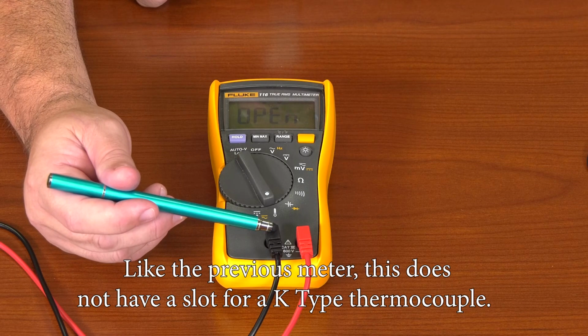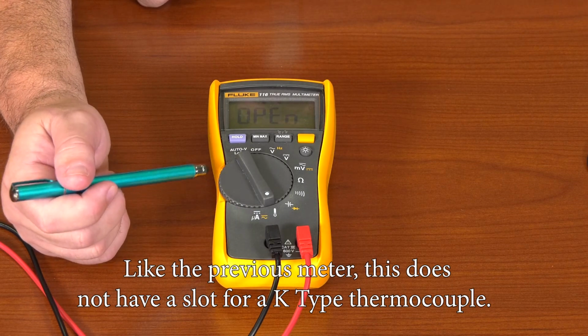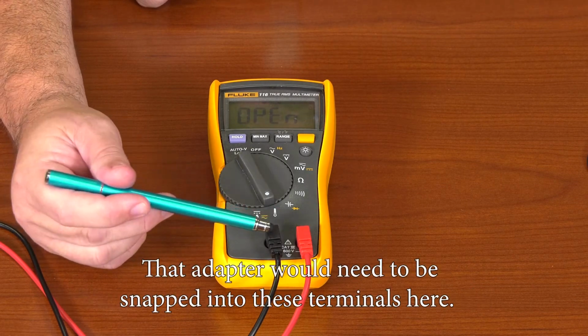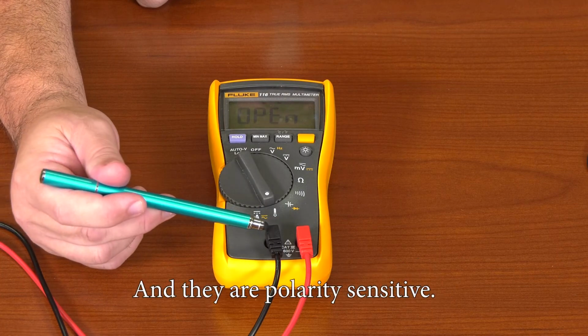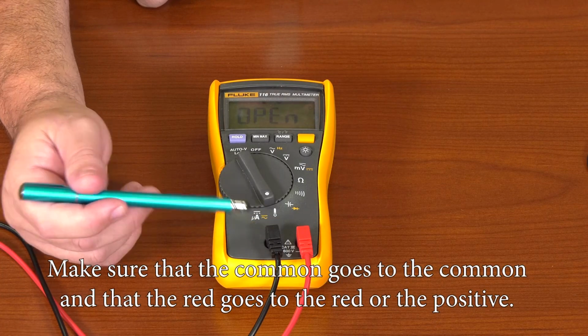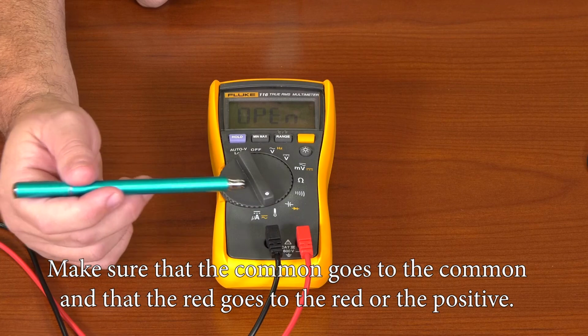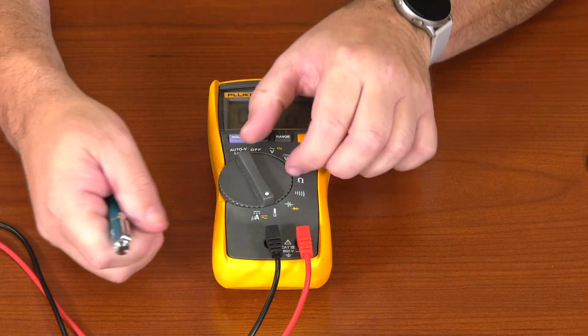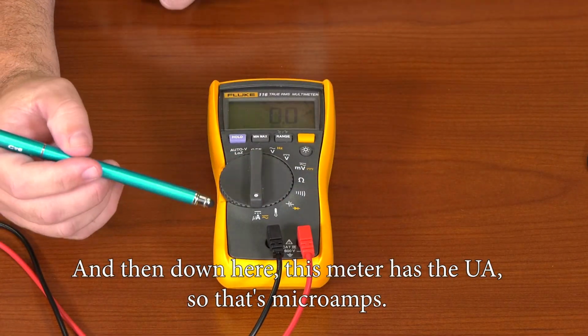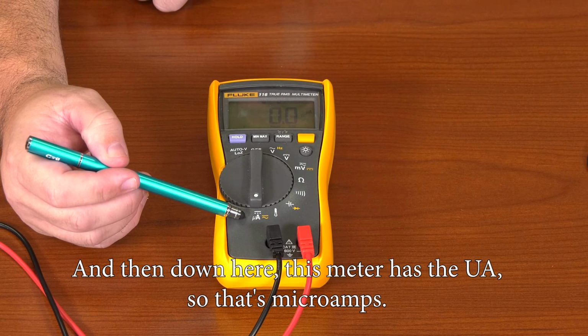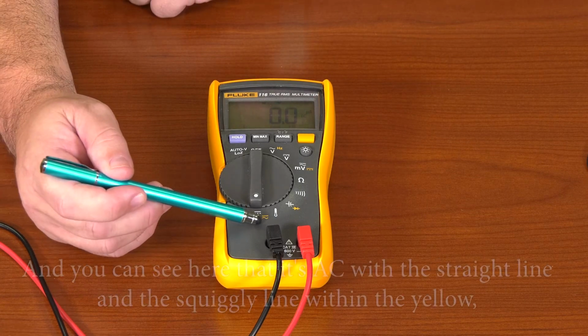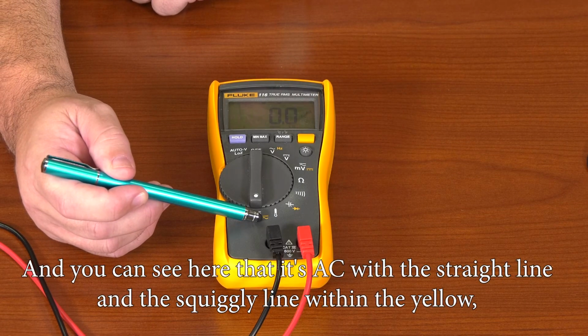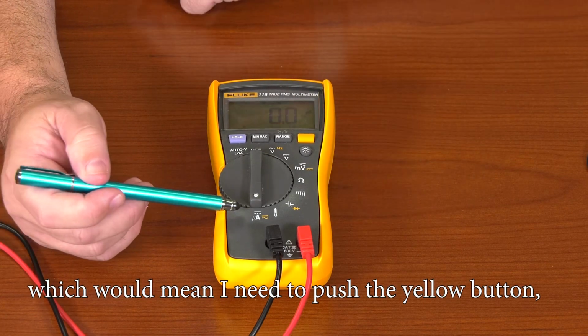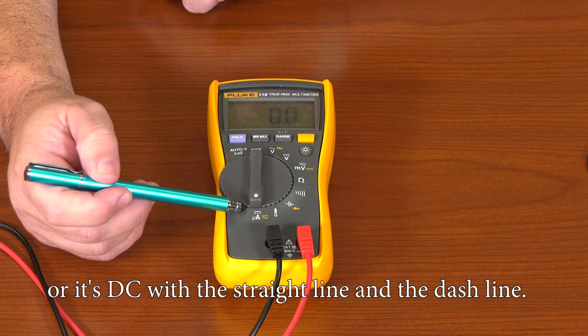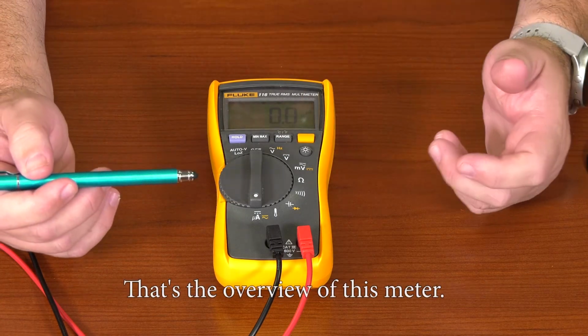Like the previous meter, this does not have a slot for a K-type thermocouple. That adapter would need to be snapped into these terminals here. And they are polarity sensitive. Make sure that the common goes to the common and that the red goes to the red or the positive. And then down here, this meter has the uA, so that's microamps. And you can see here that it's AC with the straight line and the squiggly line within the yellow, which would mean I need to push the yellow button, or it's DC with the straight line and the dash line. That's the overview of this meter.